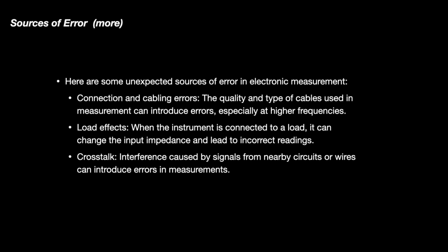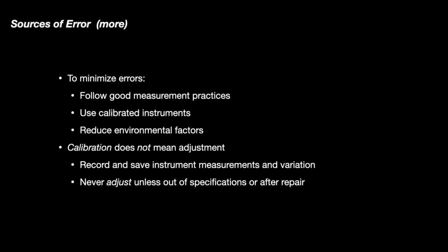And finally, crosstalk. And there's probably a lot of it that you deal with, because we're dealing with electrical machinery, industrial machinery out on the field, like even the solar stuff, has, particularly if it has its own internal communication network, the proximity of wires can transfer by capacitance a radio frequency signal onto what you're trying to measure and just plain DC. So good measurement practices, use calibrated instruments, and keep the environmental factors in line, and that gets you 50% of the way there.